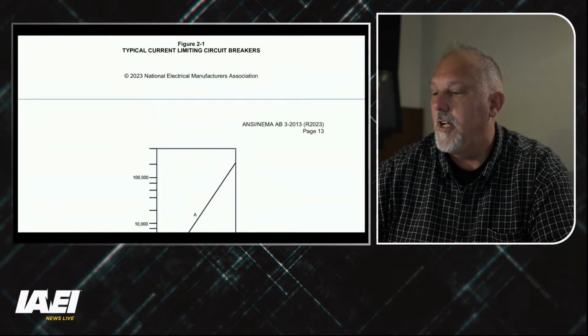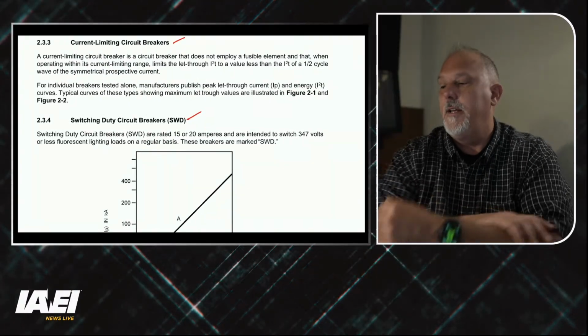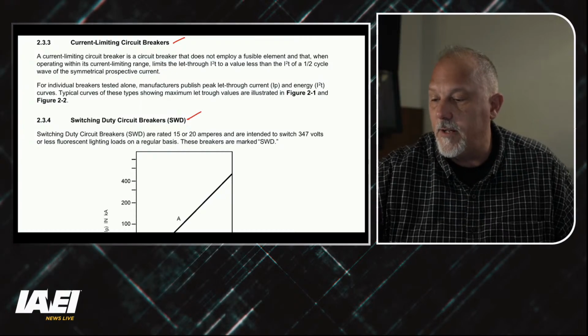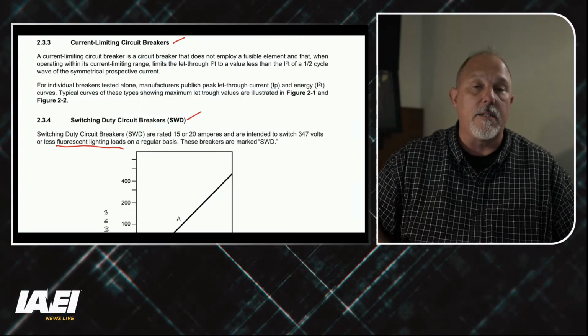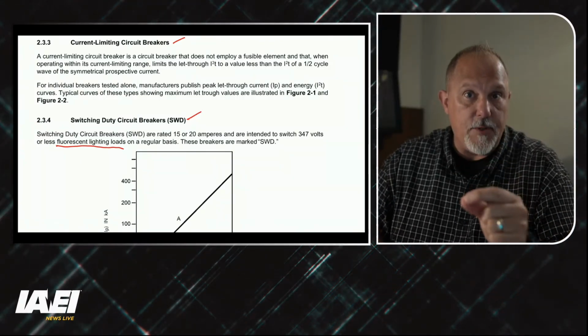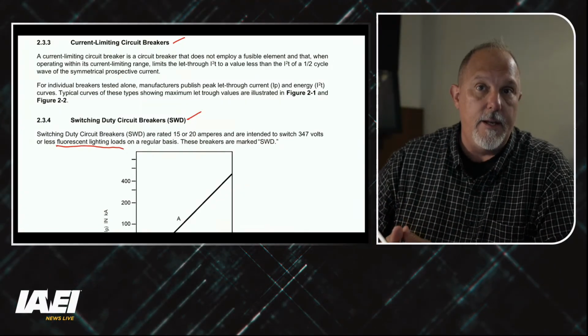They don't say much, but in for a switch duty, circuit breakers are marked SWD. Oh, they do. Here it is. That's what I was looking for. Fluorescent lighting loads on a regular basis. So when we see the reason they came up with SWD, they did a couple things in the testing in UL 489.